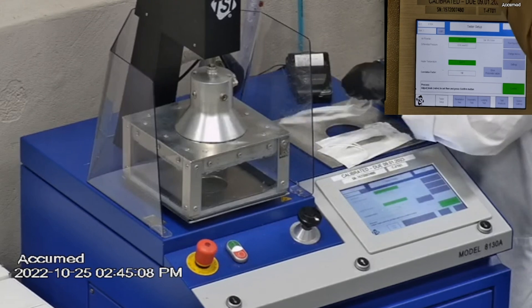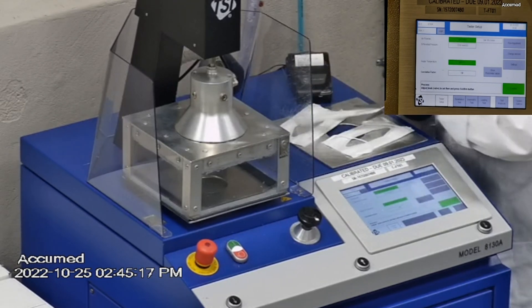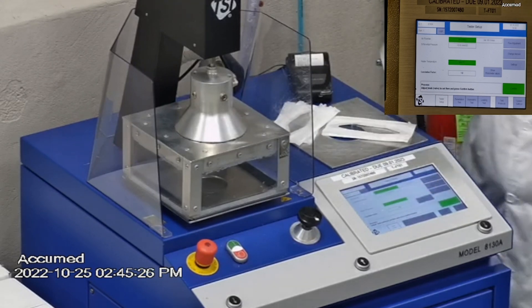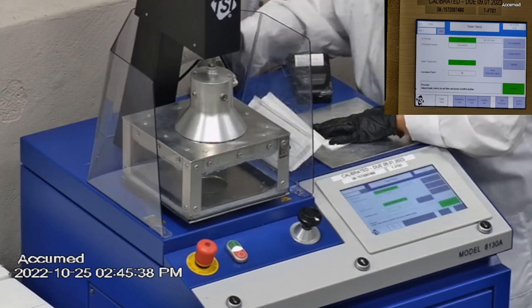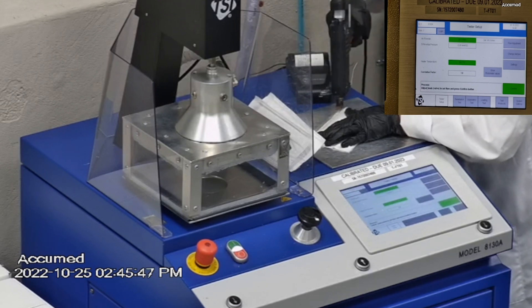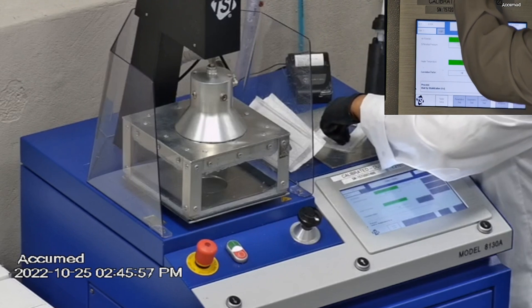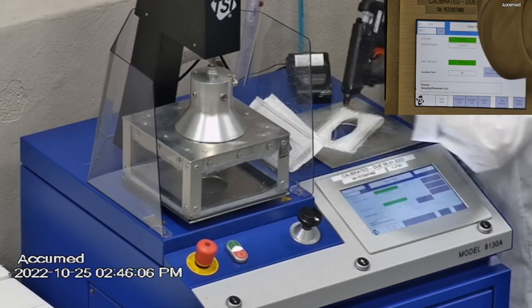The 8130A is the same filtration testing machine that NIOSH uses to approve N95 respirators. Our procedure is also inspired by NIOSH. We first run a tester setup and start removing the headband from the respirator before placing it onto the testing plate to ensure a proper seal. Then we make sure that the mask is properly and completely sealed with glue to the testing plate. When applying the hot melt glue we make sure that there are no holes or leakage around the seal to ensure accurate results. The testing plate is then attached to the frame and the box is placed under the TSI filter holder for testing.